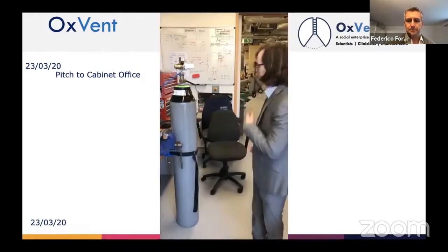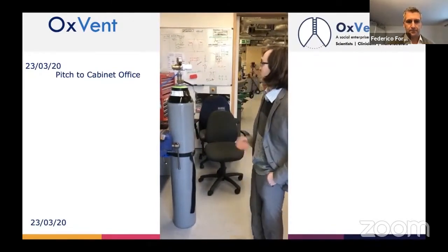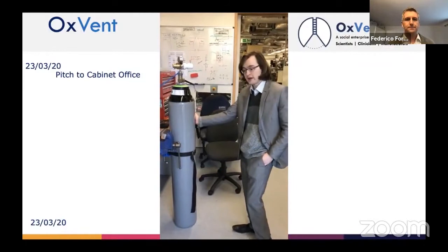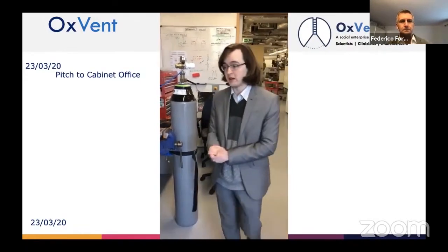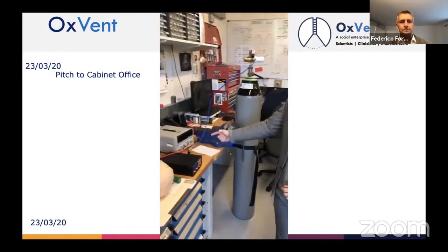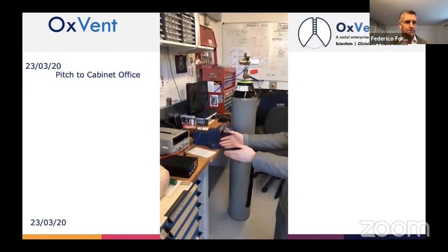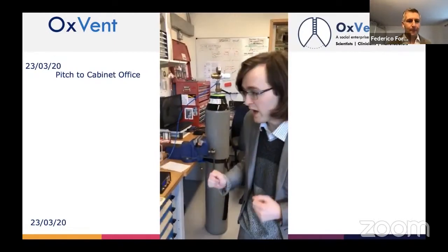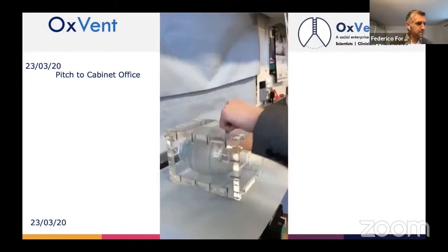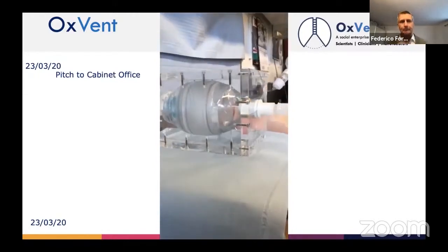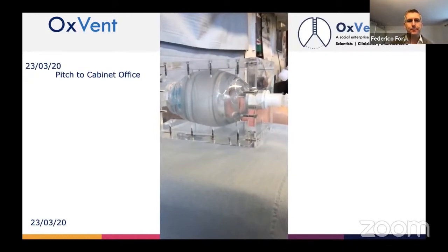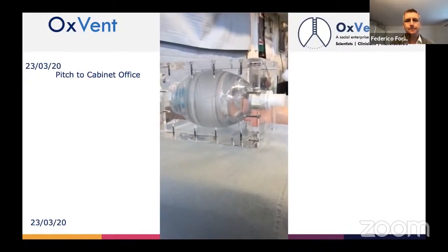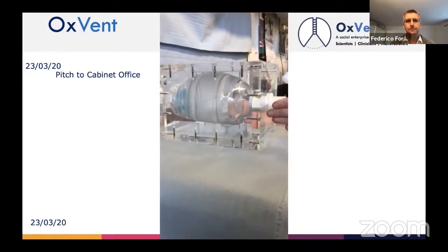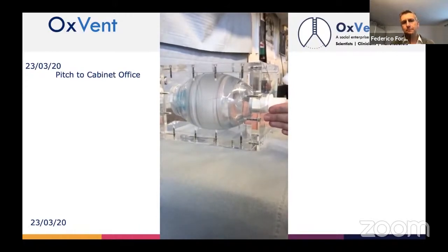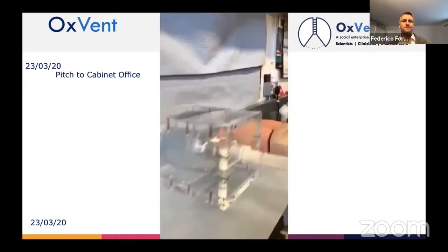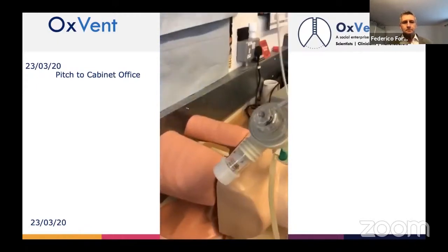Allow me to present the OxVent. This system takes in standard 4-bar air, here supplied by a canister, but available as standard in all NHS hospitals. This comes through a small solenoid valve with an electronic control system, more on that later, and is driven into this box. Inside the box is a standard ambulance bag. These bags are normally compressed by hand to provide air to a patient, but in this case we compress it using the pressure from our air supply. This is then used to ventilate the patient, and a valve allows the patient's lungs to relax.